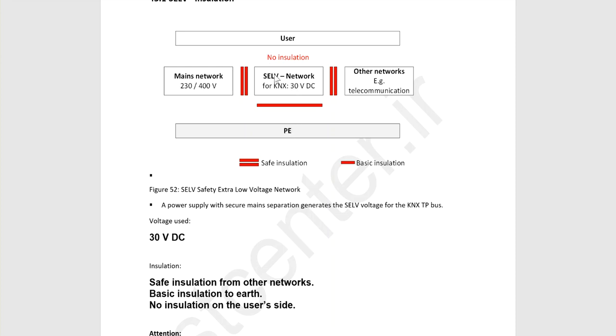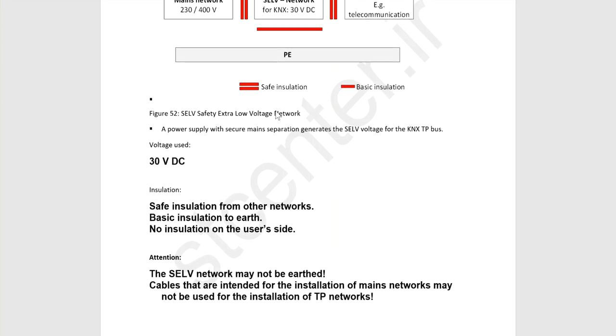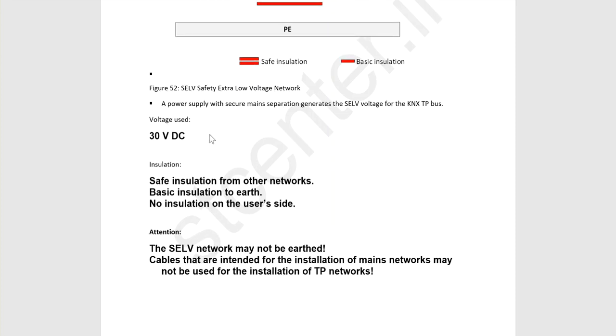So you can see here there is no insulation between the KNX devices and the user, because the KNX devices are SELV and you can work by hand in a safe manner, as we do in a project. For example, we wire the black and red KNX cable to the KNX connector without using special tools. So the voltage we use is 30 volts DC.